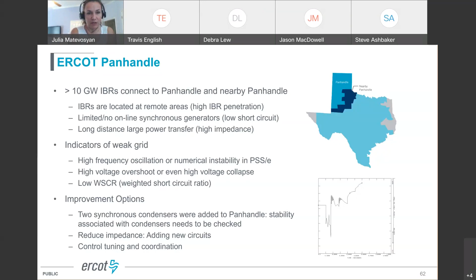We tried several improvements in this area and installed 2 synchronous condensers. Even though it helped with the weak grid situation, it had its own stability issues. I'll talk about it later. Another way is to reduce impedance by adding additional transmission circuits, and also some improvements that Jason, I believe, mentioned can be achieved by controls tuning and coordination of controls of inverter-based resources in the area. We can go to the next slide.